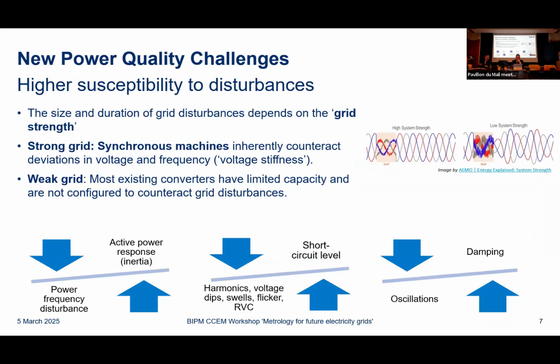You can have an emission into the grid, but the impact on the grid depends on how long and how big that disturbance is going to be. And that depends on how strong the grid is. A lot of people talk about grid strength, and if you have a lot of synchronous machines, in general, that is a strong grid because they inherently will counteract most types of disturbances. They provide a kind of voltage stiffness because they have this stored energy. The big synchronous machines, we already heard about inertia this morning. If there's a fault, they can inject and maintain a lot of current, which prevents the voltage from collapsing.